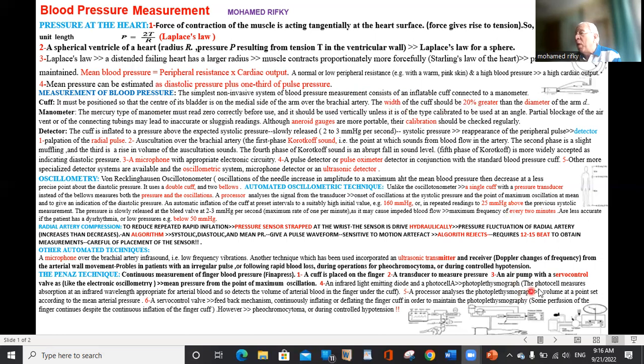The width of the cuff must be 20% greater than the diameter of the arm. You see, we'll show it in a bigger figure. So the width is 20% greater than the diameter of the arm to get a proper measurement. The monitor, of course, is a mercury manometer. The zero must be correctly positioned, not inclined, but if it is calibrated to be inclined, well and good. Of course, partial blockage of the air vent may lead to sluggish readings, and the upper part filter must be removed to clean the dirt accumulated upwards.